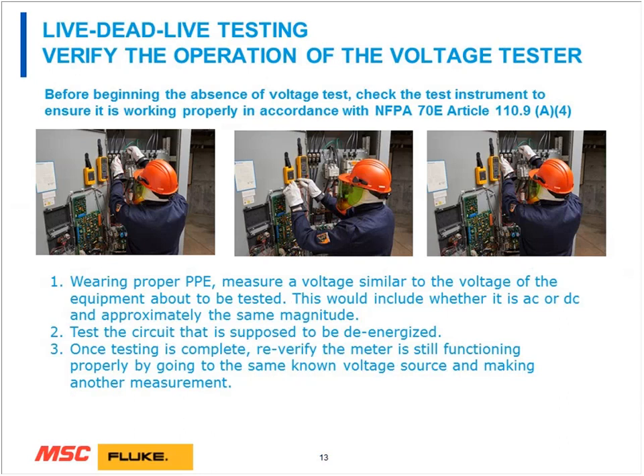So let me show you what that looks like. Here we have the live-dead-live testing being done. Again, wearing the appropriate PPE, you measure a voltage similar to the voltage of the equipment that is about to be tested. And 240 volts is sufficient in most of the panels that we're measuring. So you verify the operation of the instrument. Then touch the unknown circuit and make sure that the instrument is reading 0. Then you re-verify the operation of the instrument on the known voltage source. That's the only time that you should take off any PPE, once you've fully checked to make sure that it's deactivated.